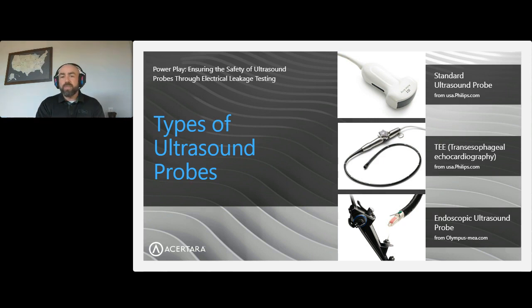The TEE probes that are probably a lot more common to see in sterile processing, you can see pictured here in the second image down, the middle image there. TEE probes are phased arrays. Some are capable of 3D imaging, some are not. They're typically used in planning valve replacements or during open heart surgeries to keep the ultrasound image available and the data available to the physician. But let's say you're doing open heart surgery. Now the ultrasound probe is down the patient's throat, and they're able to image the heart from very closely through just a small amount of tissue so that they can achieve the best image and not interfere with the surgery.